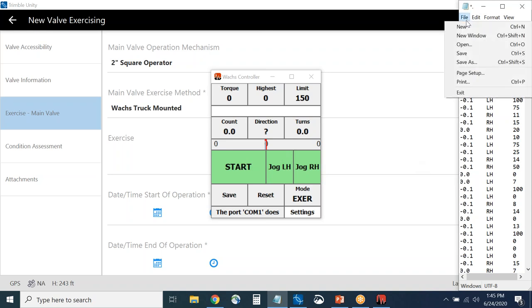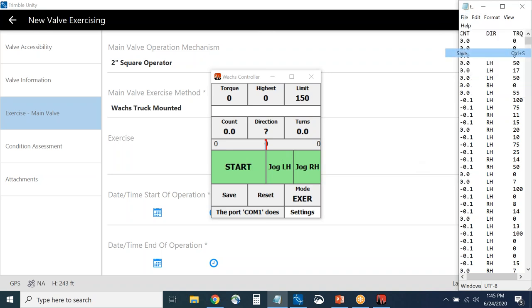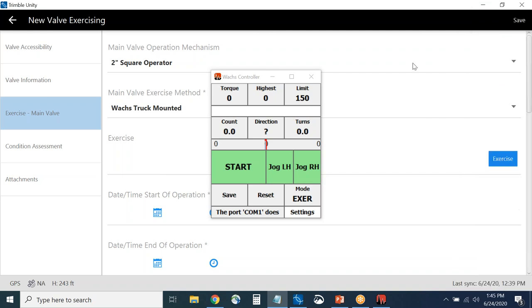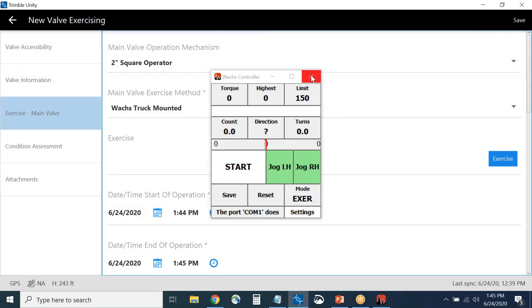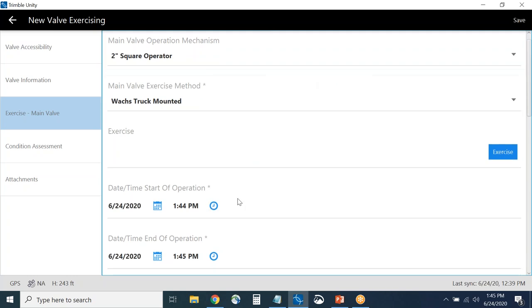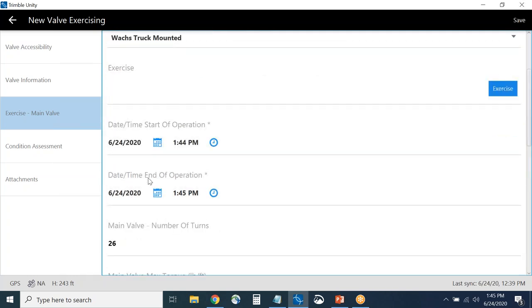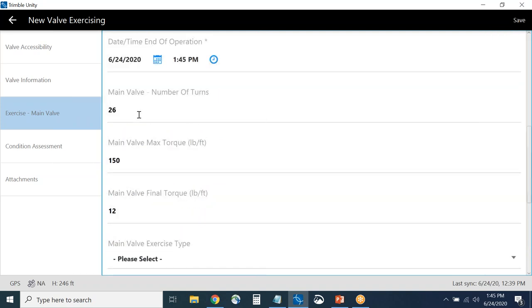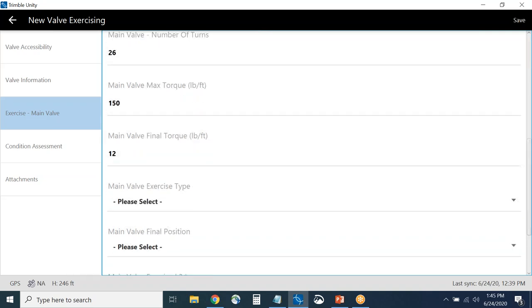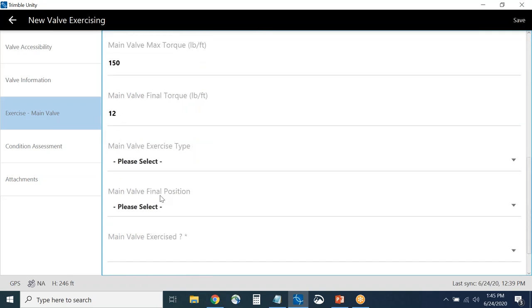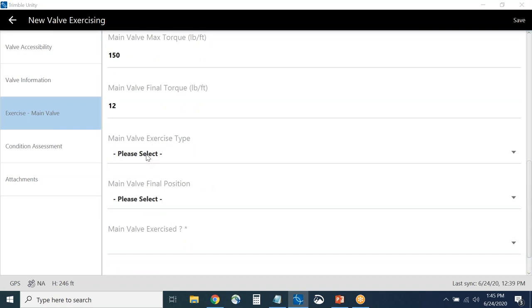When I fill that information out and close the controller, it automatically calculates the start and end of the operation, the number of turns, the maximum torque, and the final torque. Then a couple of very important questions: what type of valve exercise was done — a full exercise — what was the final position — opened or partially open — and was the main valve exercised. These questions support the entire valve exercising workflow.